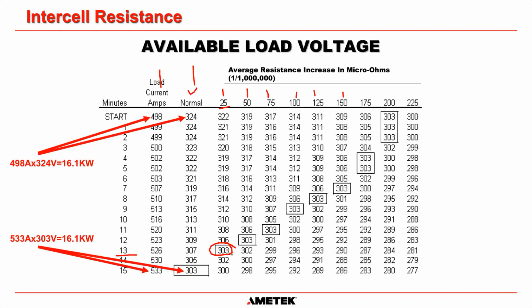Okay. Now, many people will say, well, 15 to 13 minutes, that's not excessive. But what you will see is as you go along here, when you increase the average connection resistance by 200 microohms, as soon as you start the test, the voltage of the battery is going to go down to 303 volts, which is its end voltage, and therefore the battery has no capacity. It's going to seem like it has no capacity because all the voltage is going to be dropped across those resistors, and all the power is going to be dropped across those resistors.